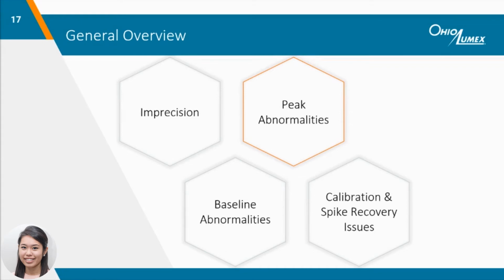Generally, baseline abnormalities are uncommon after the instrument has stabilized. If baseline issues are still present after substantial warm-up time, transport the instrument to another location with minimal temperature fluctuations, or replace windows if sine waving occurs. Peak abnormalities are more common than baseline abnormalities during analysis. Flip to page 8 of the Guide to Troubleshooting and Preventative Maintenance to continue following along.